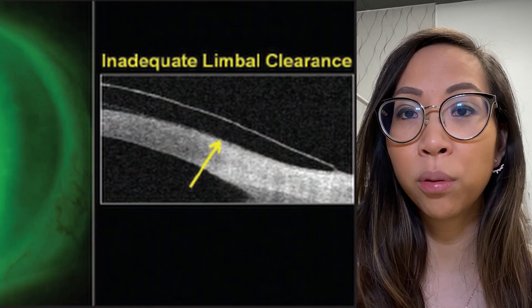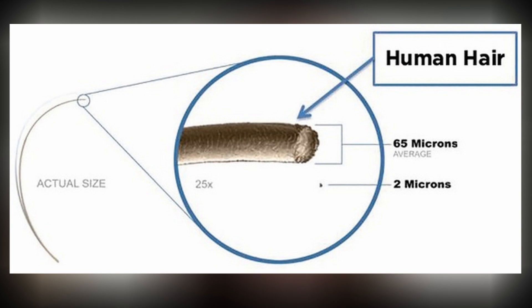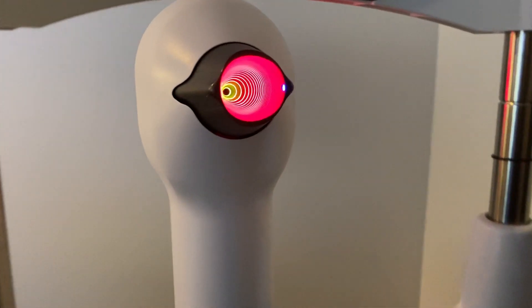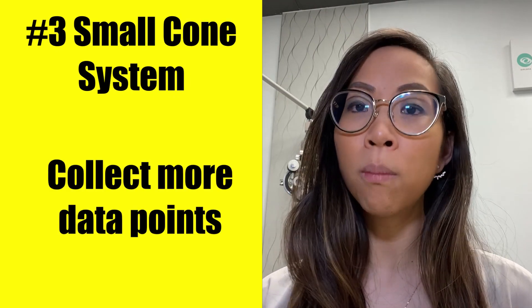This is important especially when fitting scleral lenses. These lenses not only vault entirely over the cornea, but you also need to clear the limbal zone. So knowing the shape of not only the cornea but also the limbal zone is critical when designing the lens and determining the overall diameter. The Medmont E300 is also extremely accurate, with a standard deviation of error of less than 2 microns. To put that into perspective, the average human hair thickness is 75 microns. This topographer is known as a small cone system because of its smaller cone design compared to large cone systems, and small cone designs collect more data points and are ultimately more accurate.